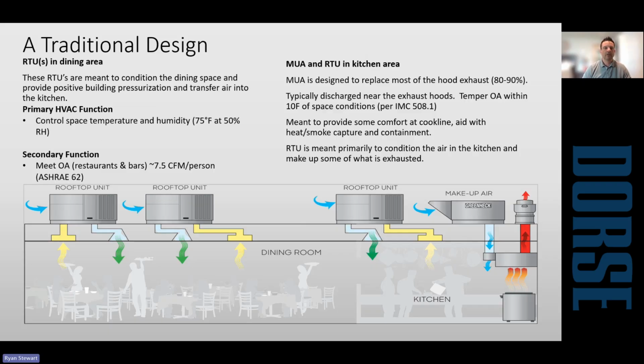So in a traditional design, you'd have your RTUs in the dining area. They're controlling space temperature and humidity and providing the minimum outside air requirements based on ASHRAE Standard 62. And then back in the kitchen, you would have a makeup air unit. Code says it needs to be capable of providing 90% of the exhaust, but you typically see in the 80 to 90% range. You're usually going to condition the makeup air within 10 degrees of space conditions. So in Western Washington, you're going to heat it, potentially do some cooling. In Eastern Washington, you're going to see heating and cooling. And as a part of that makeup air, the way it's introduced with the compensating hood also helps provide an air curtain to aid with capture and containment. And then you have an RTU or ducting from RTUs that help condition the kitchen area.